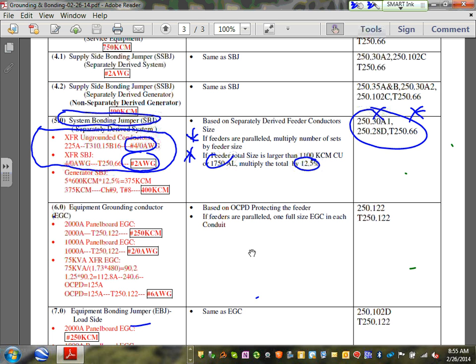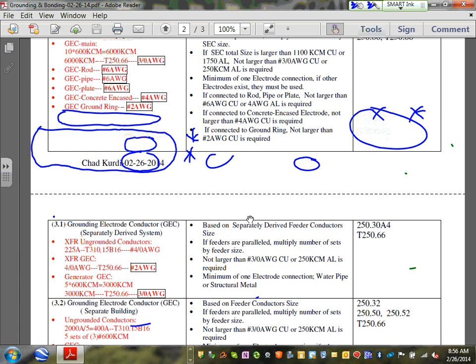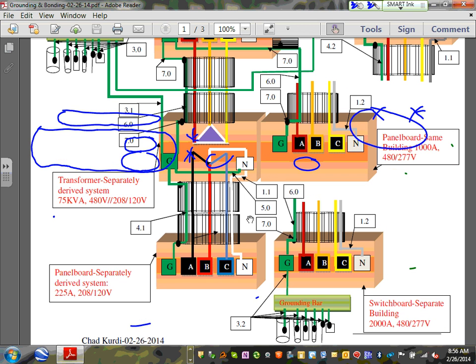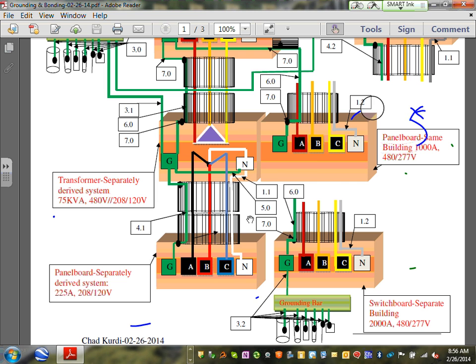Okay, so that's the system bonding jumper. Any questions, guys, about the system bonding jumper? That's how you bond, Adam, the neutral of the 120 to the ground inside the transformer. With one conductor, number 2. One conductor, number 2, system bonding jumper. All right, so we did 2 things, gentlemen and ladies. I want to remind you quickly, as we're walking through this, here's what I did. I sized the neutral, and I also sized the system bonding jumper.